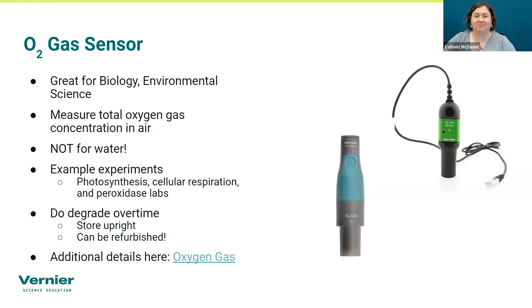What we can actually do is look up the age of your sensors, and also tell you the state of the electrochemical cell in your sensor. On the website, we also have a user manual and information facts for these sensors with that information, along with how to properly calibrate, because like the pH sensors, these do decrease in calibration over time just due to age. So they'll want to be recalibrated every so often the older they get.